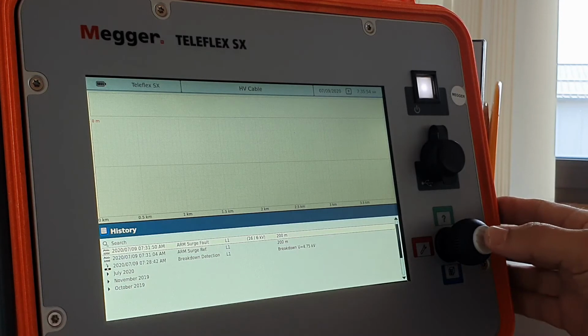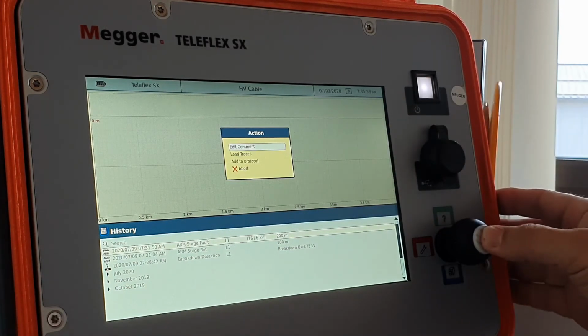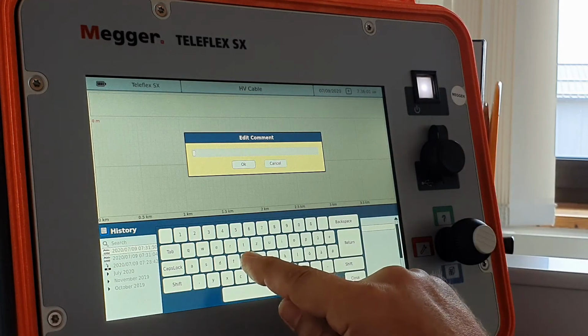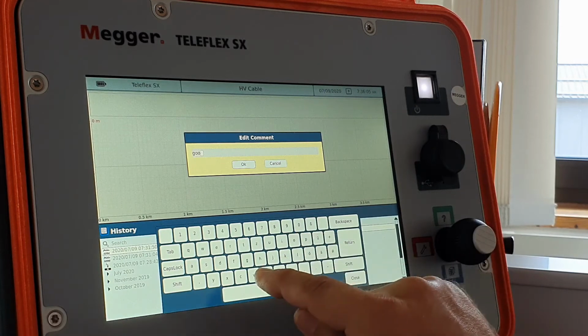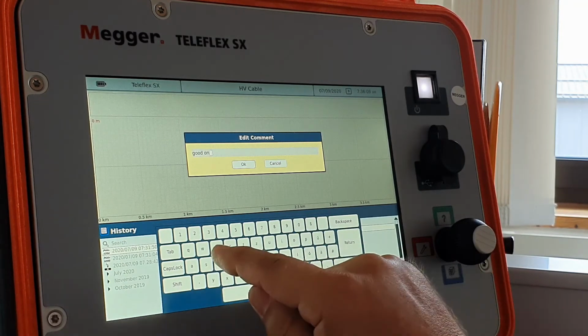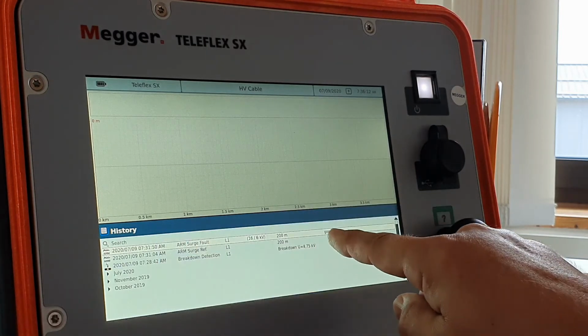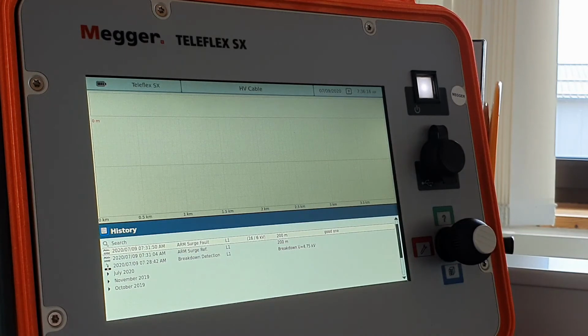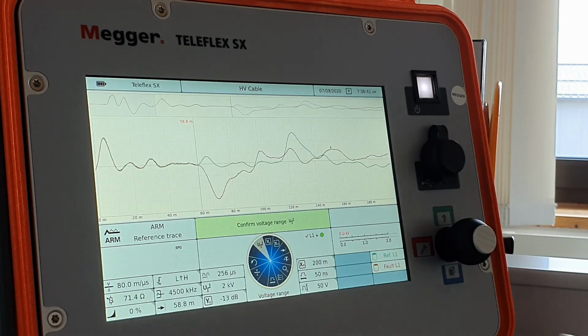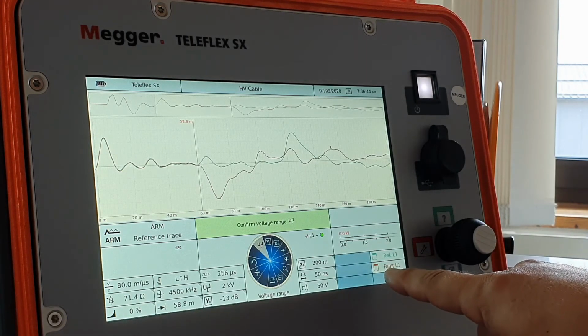If that is not enough information for me, I can simply edit a comment and say good one. Okay. And here is my comment. So if along my fault locating I want to go back to a measurement that I did an hour or 2 hours ago for comparison, I can do that. And if I have many measurements, I can even distinguish them by the settings or by a comment that I enter. And here's my measurement from a moment ago. I see now from the barrel symbol that it comes out of memory.